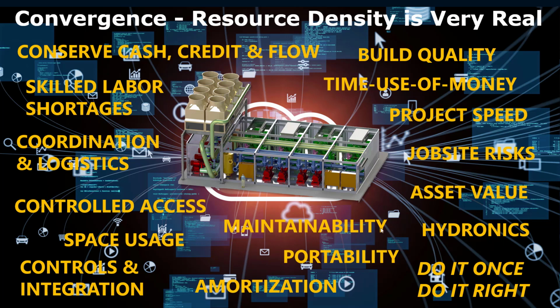Maintainability. A modular system is easier to maintain, again pointing towards this convergence towards modular construction. Portability. A module can be moved to a new location for a plant expansion, for example, or reduction in plant size. We talked about the amortization. This is actually something that is a beautiful incentive to buy a modular chiller plant, because you're able to take the entire plant and amortize it as one single unit in a rapid way, as opposed to a long-term amortization per square feet in an equipment room.